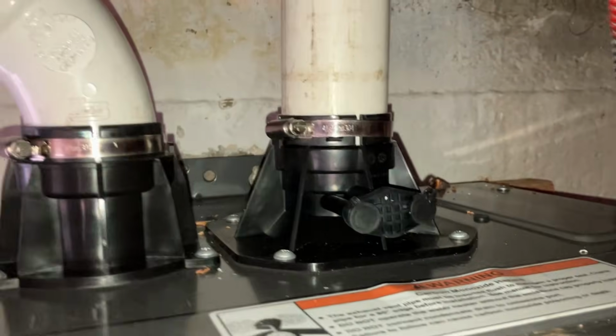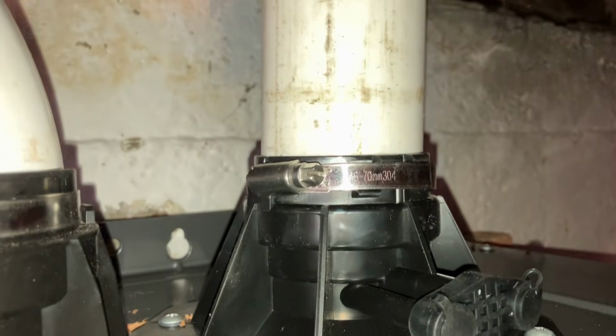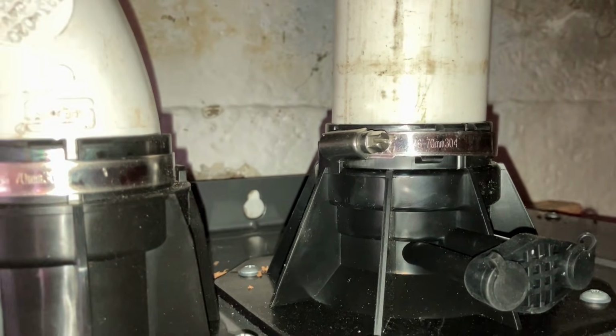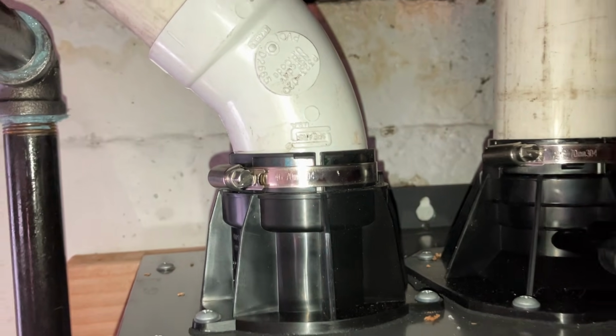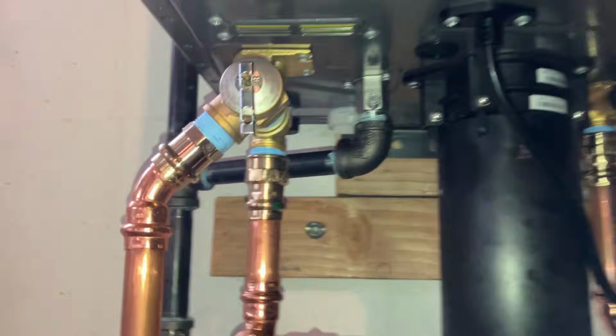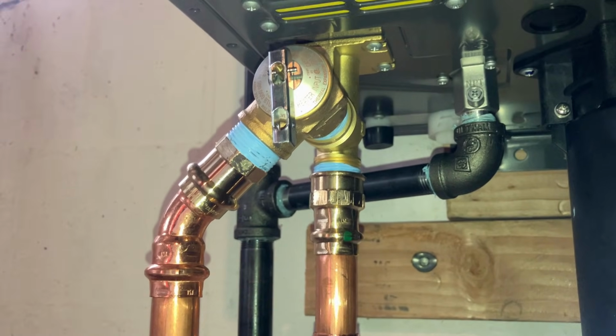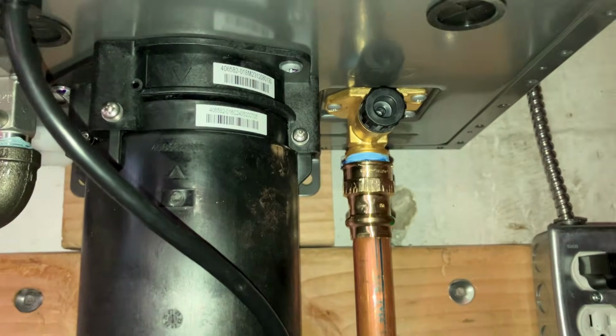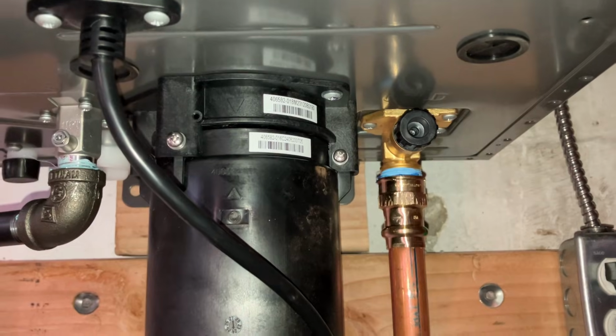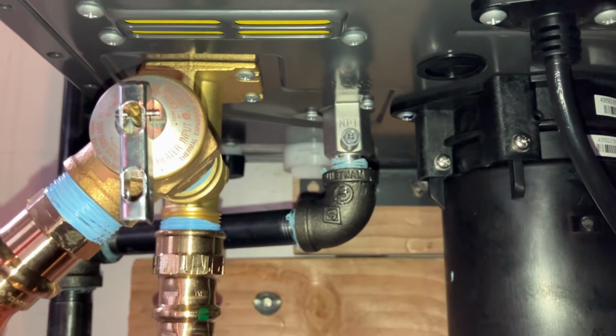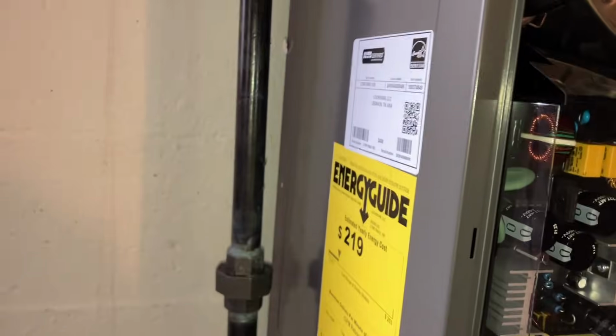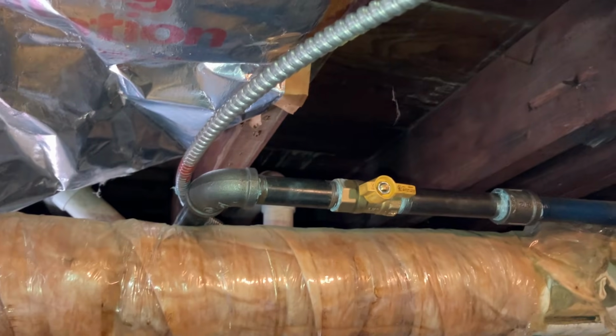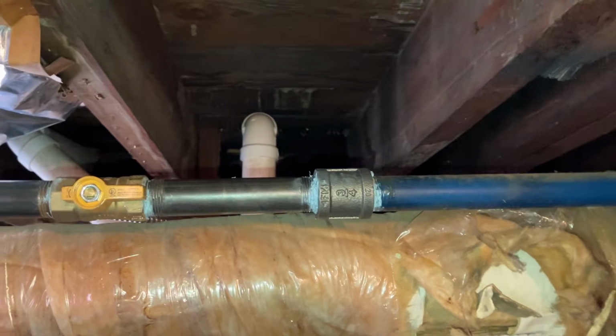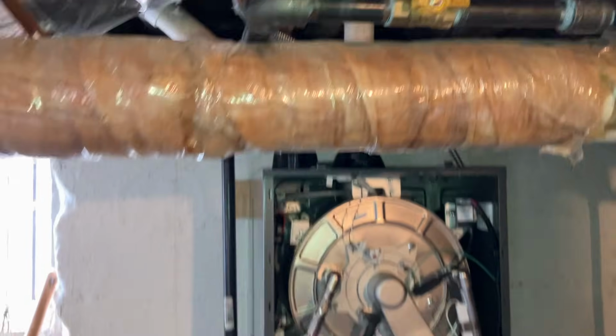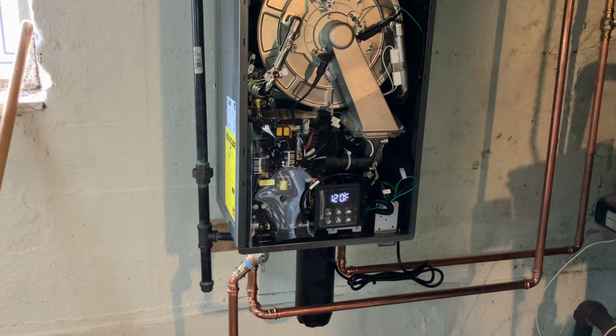On the top, we have our exhaust port for combustion and our exhaust 2-inch combustion air intake. Our water connections is going to be a 3/4 male pipe thread on the domestic hot water outlet and the inlet, so you'll be using some 3/4 female adapters. Our gas is 1/2 inch. We're going to size up to 3/4, and we have our union and our gas valve. Now remember, our old water heater was standing right here, vented into the chimney, and we just manipulated the piping a little bit to accommodate the XCalibur. It's a beautiful machine, and it's whisper quiet.